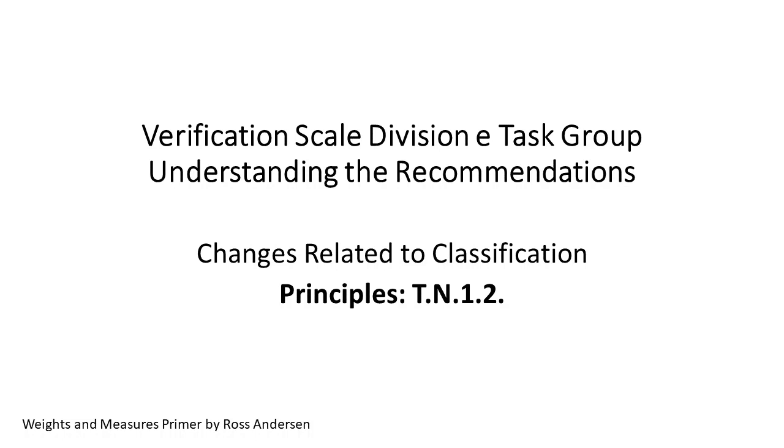You might think that classes were a new concept in the 1984 replacement code. This is incorrect. Scales were classified pre-1984, but classified by application, not design. One class included vehicle, axle load, livestock, railroad track, and hopper scales other than grain hopper. These all shared a fixed 0.2% tolerance. Many other applications had a 0.1% tolerance.